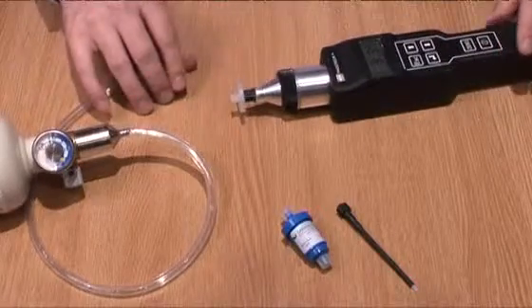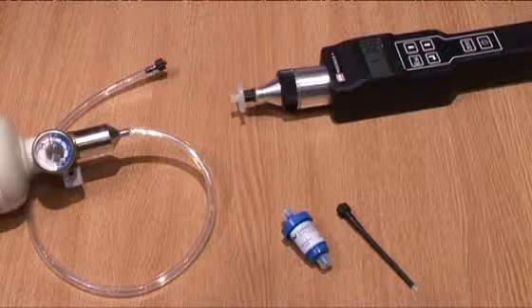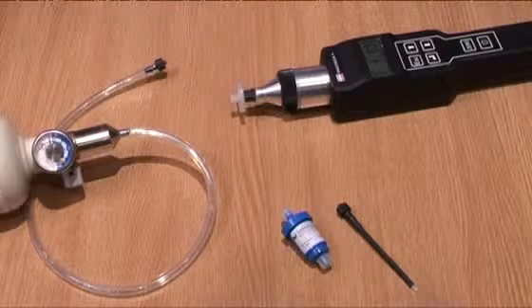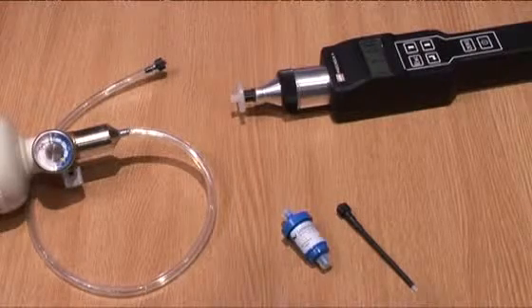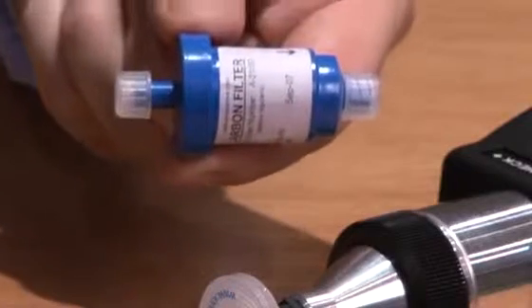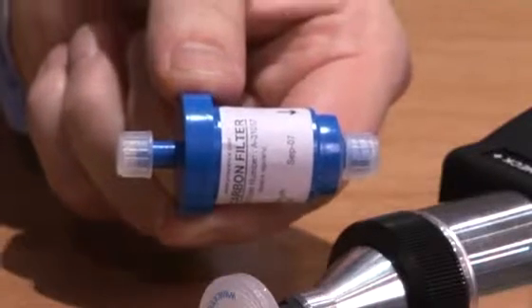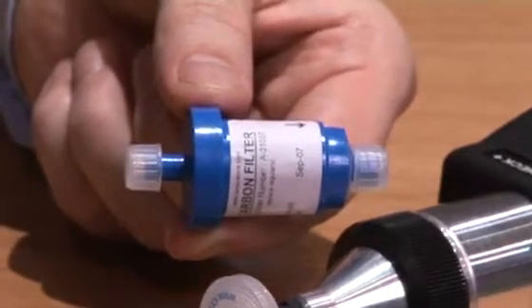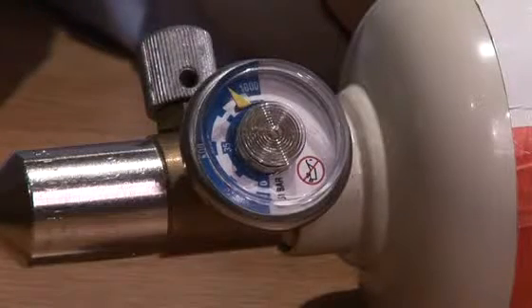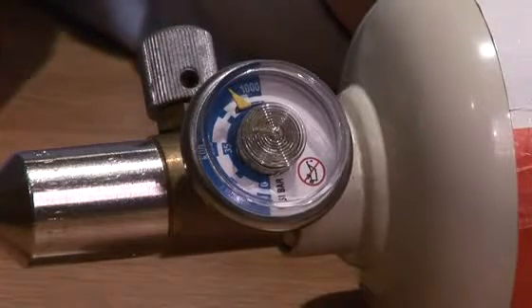Turn off the calibration gas. This completes the function test of the instrument after a calibration has been completed. If you are not successful in calibrating the instrument, check that the carbon canister is not contaminated or that the calibration gas canister is not low or empty.